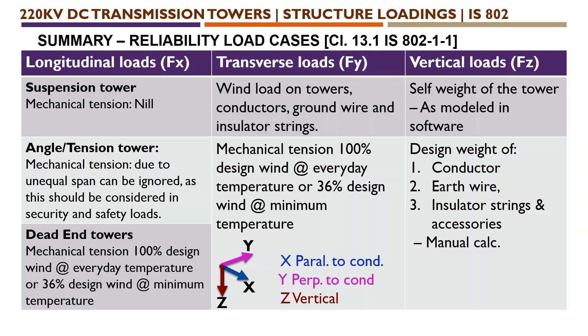For transverse loads — that is load in the Y direction, horizontal load in Y direction — we need to consider wind load on towers, conductor, ground wire, earth wire and insulator strings, along with mechanical tension: 100% designed wind at everyday temperature, or 36% designed wind at minimum temperature.